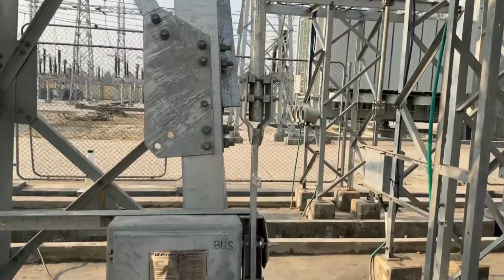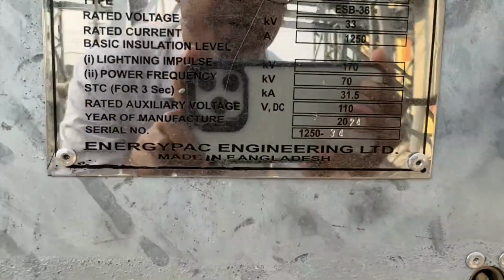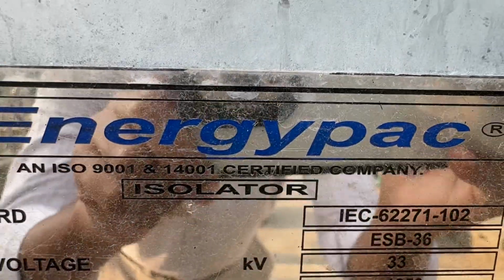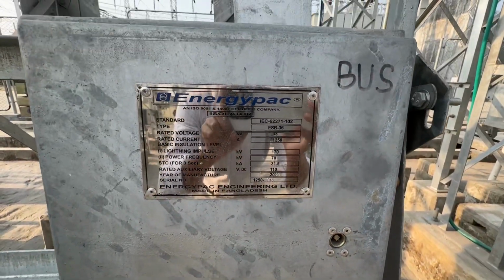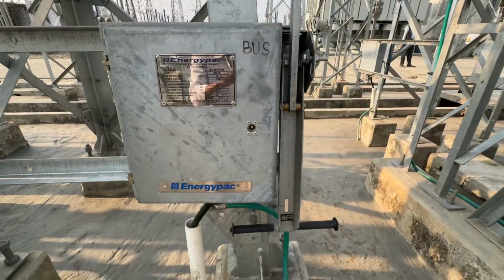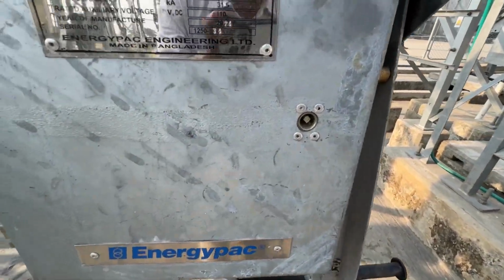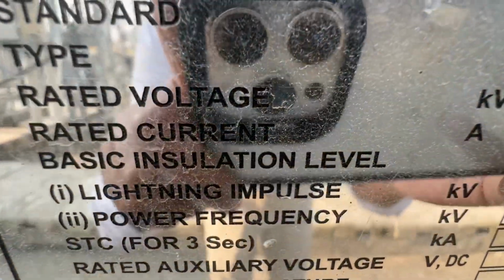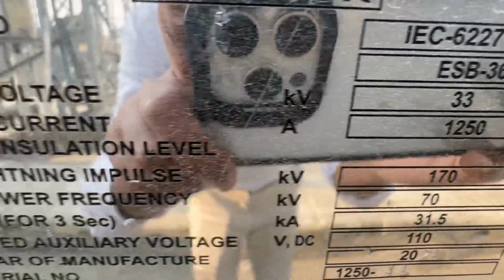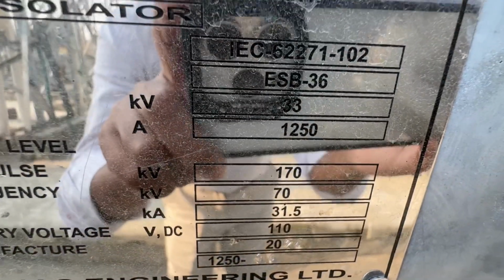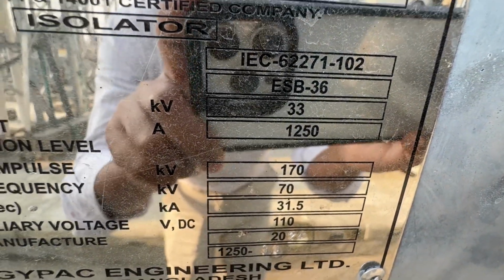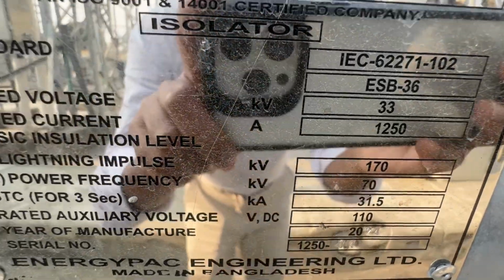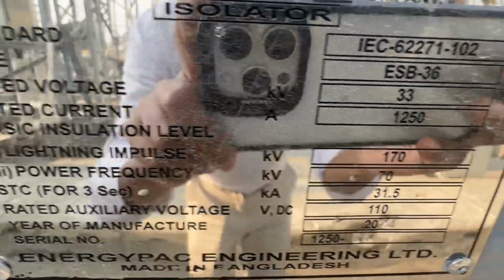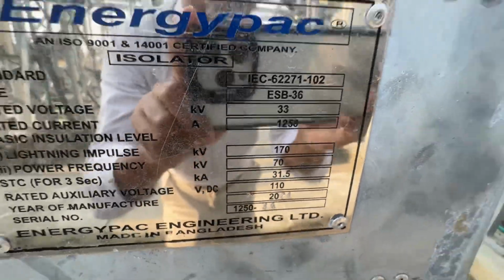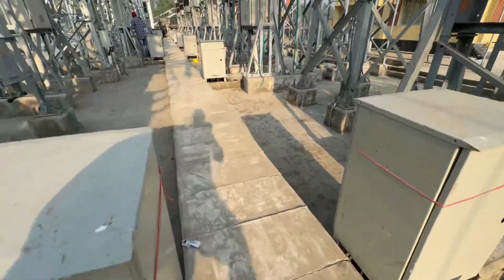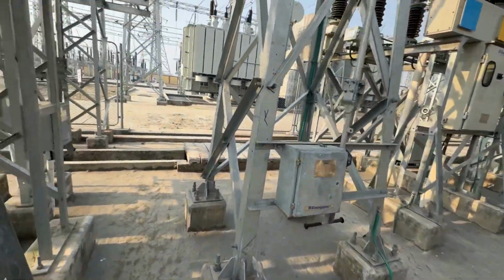This one is the 33 kV isolator. The mechanism is handle operated, no motor operating mechanism is here. Rated voltage 33 kV, rated current 1250 ampere, impulse voltage 170 kV. Okay, etc. No problem. We have to see other items.